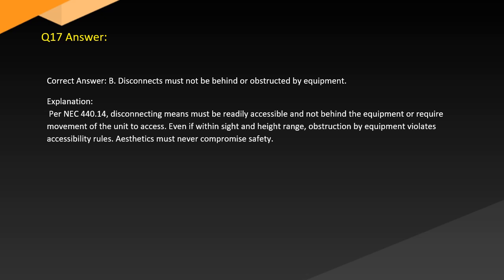Answer. Correct answer: B. Disconnects must not be behind or obstructed by equipment. Explanation. Per NEC 440.14, disconnecting means must be readily accessible and not behind the equipment or require movement of the unit to access, even if within sight and height range, obstruction by equipment violates accessibility rules. Aesthetics must never compromise safety.